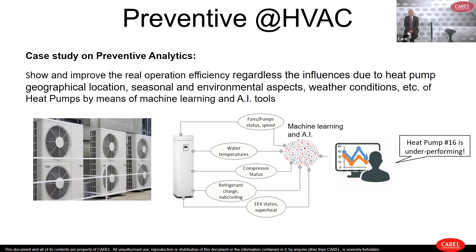So we were able, along with the manufacturer, to decide which were the most important and strategic information that we had to store and analyze in order to create the algorithm able to create a necessary output, and so to detect if there were units which were underperforming in respect of their efficiency. So thanks to these algorithms, we were able to create, as I was saying, the baseline. So create a baseline showing which should have been the expected consumption depending on the working conditions of the unit, versus the effective measured consumption.